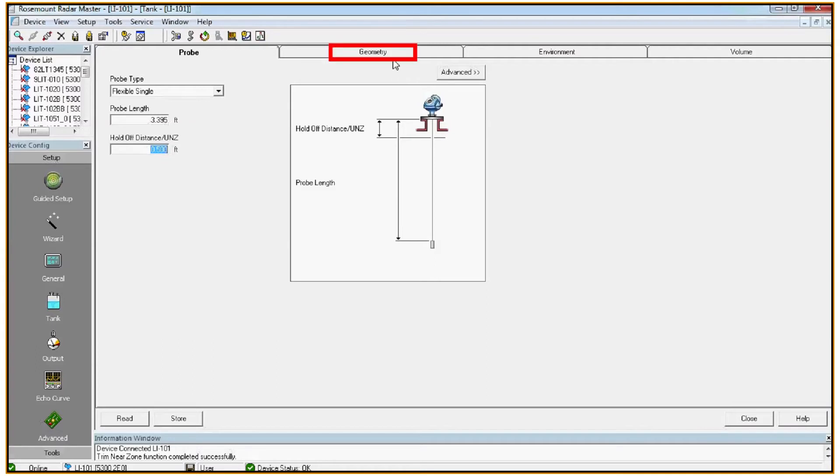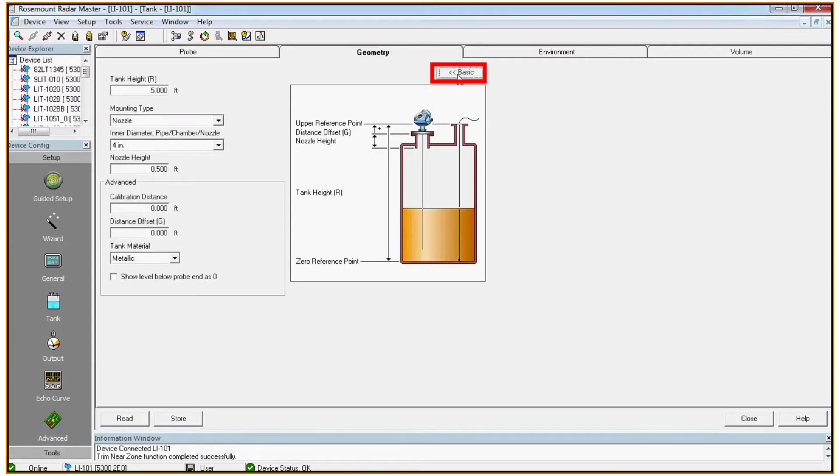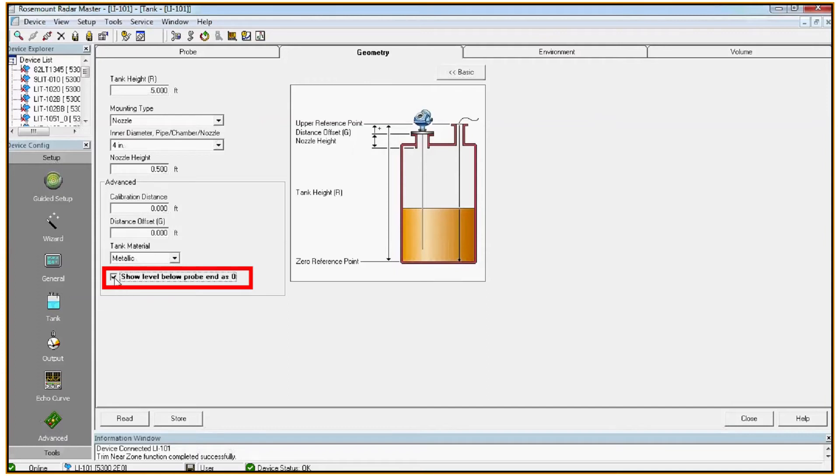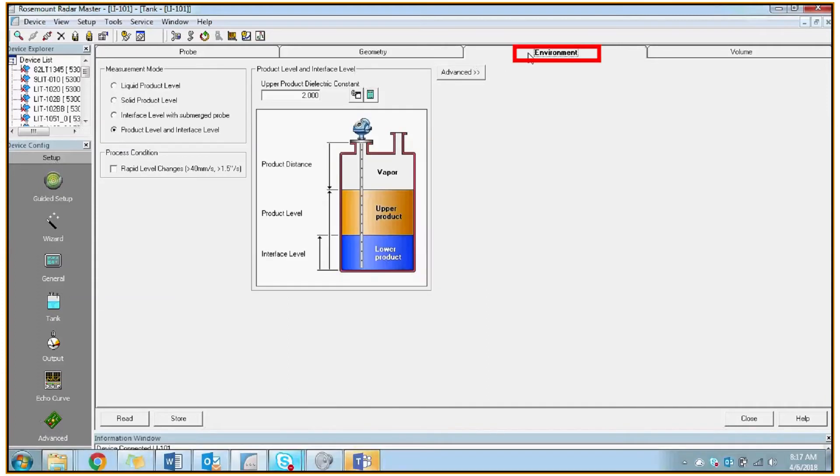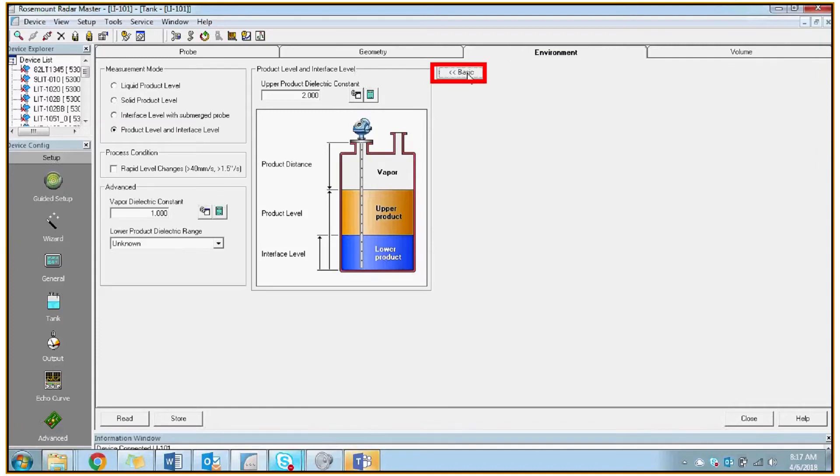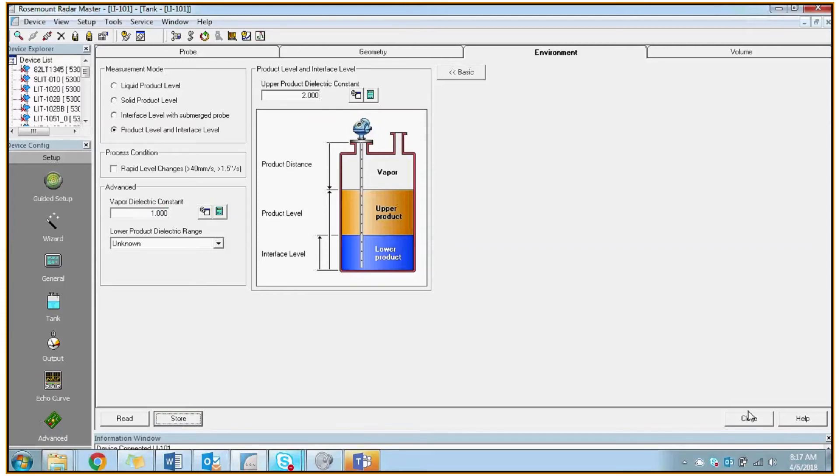Next we'll go to the geometry tab. In the advanced section we want to make sure show level below probe end is zero is checked. Next we'll go to the environment tab. Click the advanced button and we want to make sure that the vapor dielectric constant is set to one. Virtually all applications will have a vapor dielectric constant of one. If you're unsure, please call Spartan to consult. We then click store to save all our changes and close.